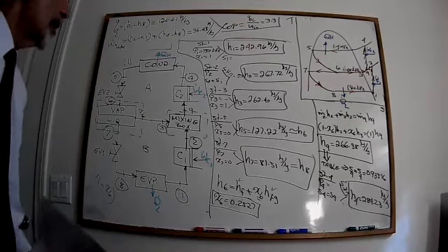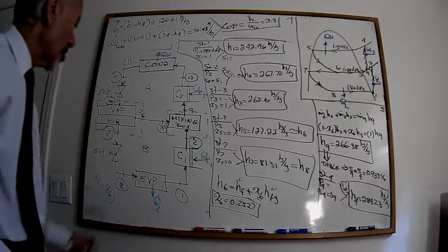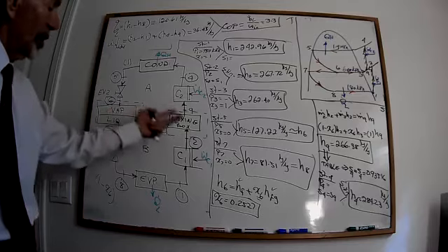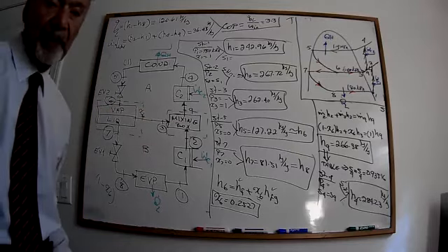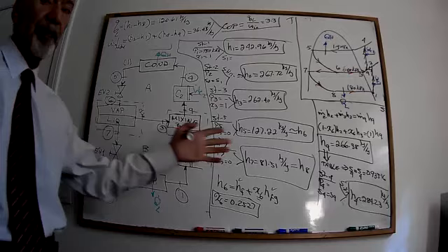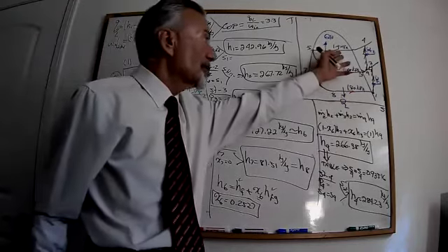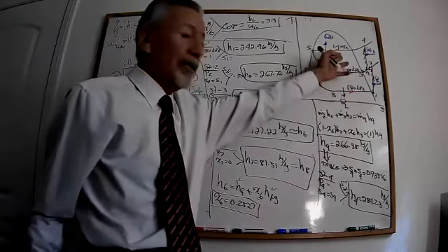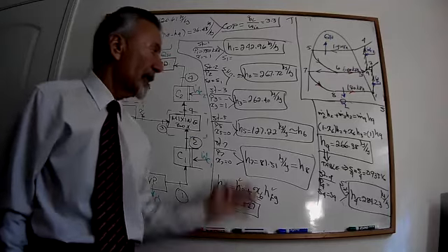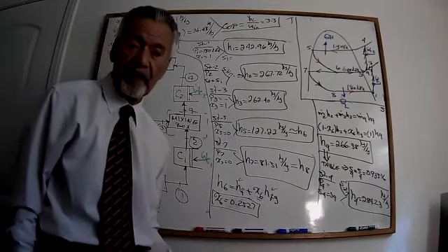Now, as you can see, going through all these costly initial costs of putting in a mixing box and flash chamber, going through the cost of maintaining and operating it every now and then, even though I increase that pressure from 800 kilopascal to 1.4, almost twice as much, look at the end, what do I have? About 1 point less than what I got in the previous example. And in the previous example, I didn't have to go through all these headaches in order to solve that problem.